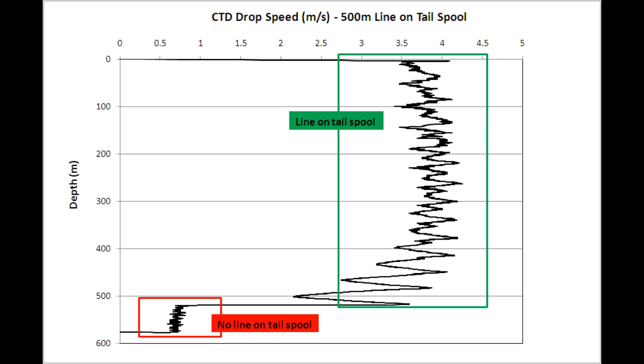The reason why it's important to keep an eye on the drop speed, and especially the change in drop speed as the probe gets deeper, is that it's a good indication of the efficiency of the rewinding process. The amount of the drop speed variation is dependent on the tension on the line during rewinding. So good profiles with the right tension on the line during rewinding, and that's about 4.5 pounds, will have a smaller variation in the drop rate, especially at the deeper part of the profile.